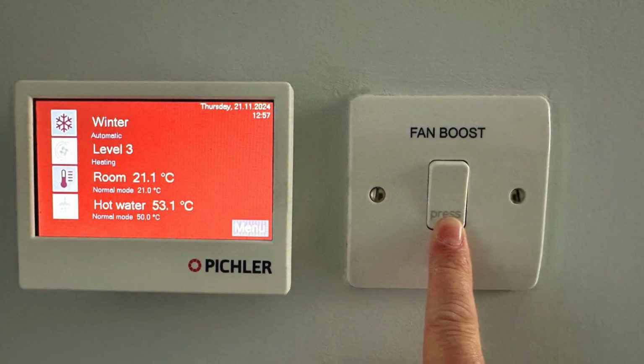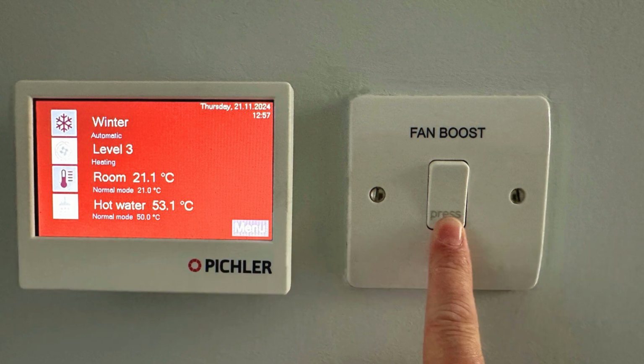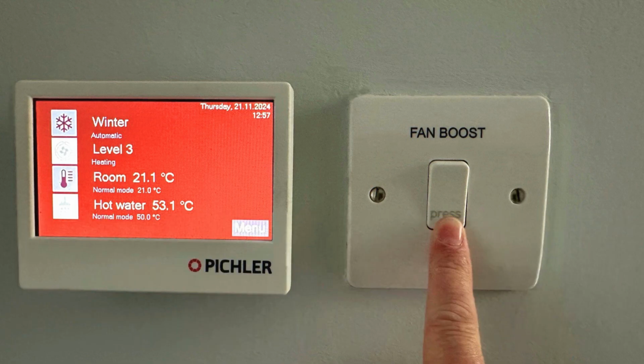Close to the controller there is a boost switch. Once this button has been pressed, it will increase the airflow to exchange the air at a higher rate for a set time of 15 minutes. If this needs to be extended, once the 15-minute duration is ended, press the button again and it will go for another 15 minutes.